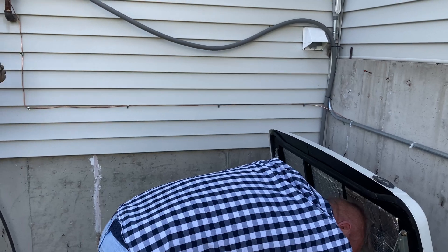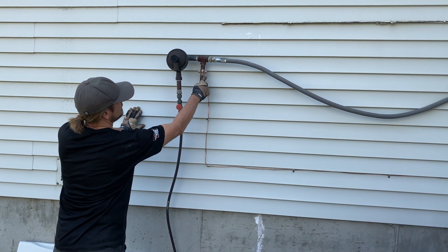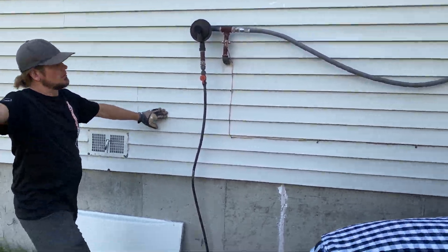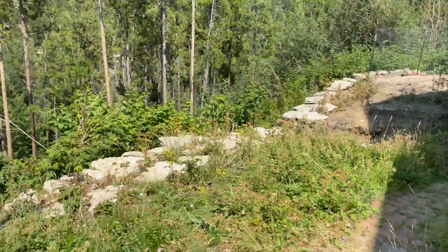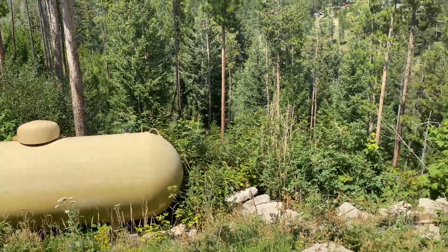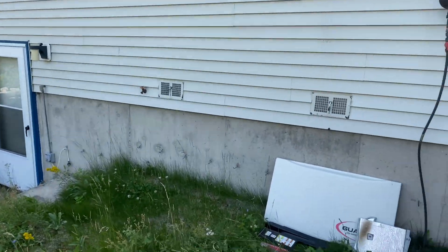We also went up here and bonded the gas valve with propane, so that comes down to his tank behind you. I'm going to show you the tank over here — today I think they have to be like 50 to 70 feet away from the house, not 18 to 20.